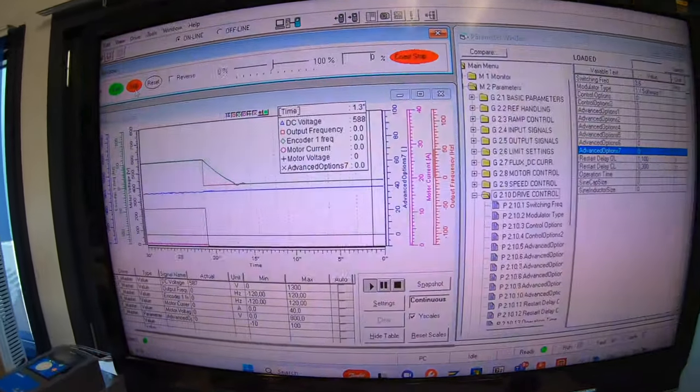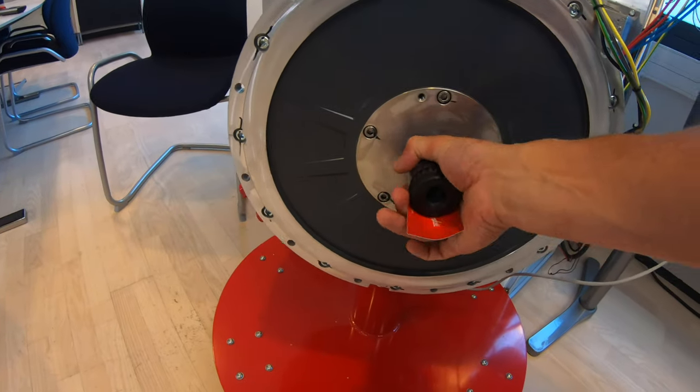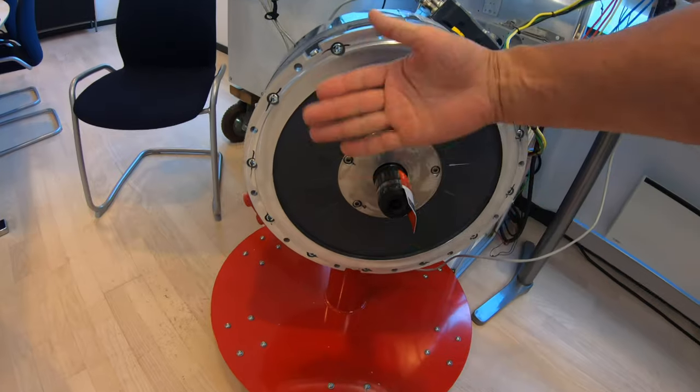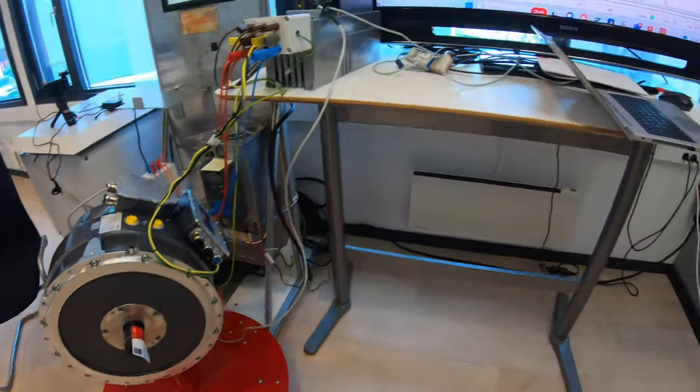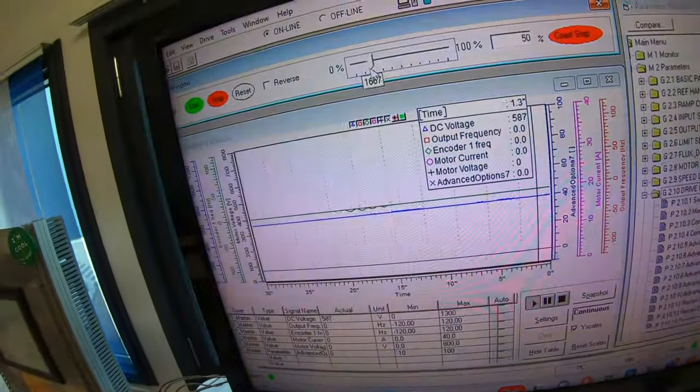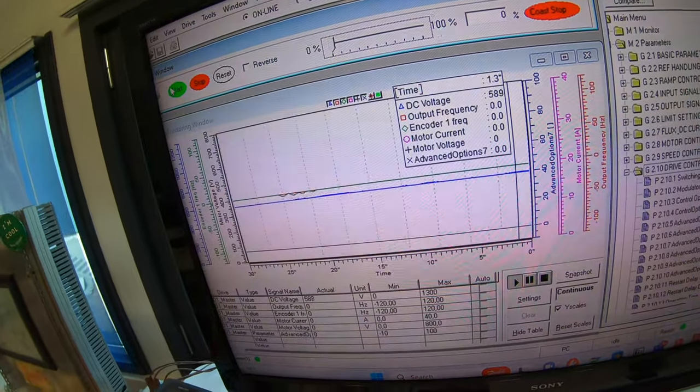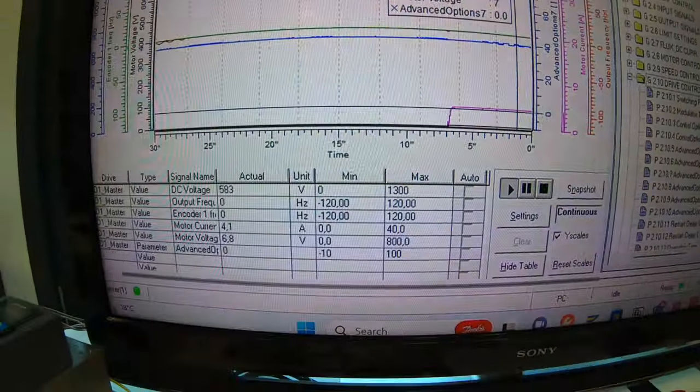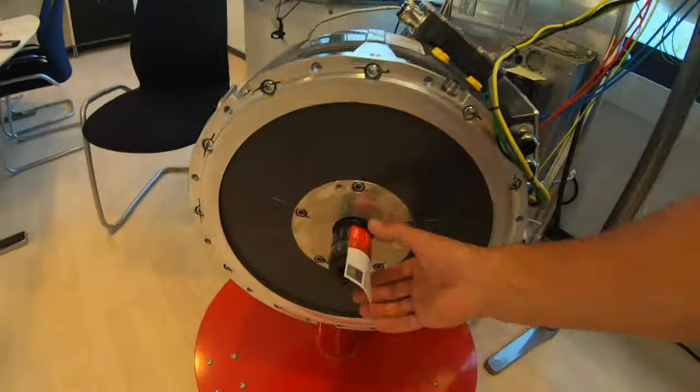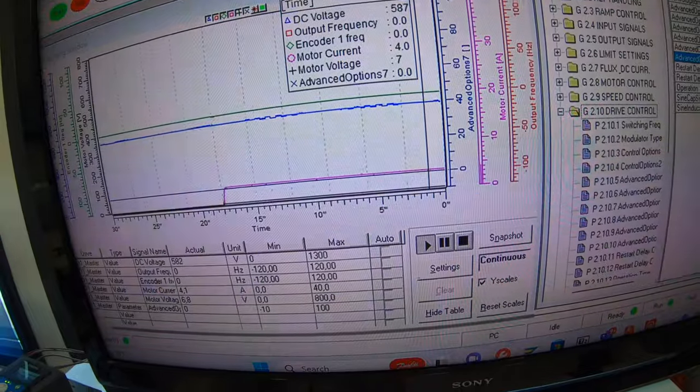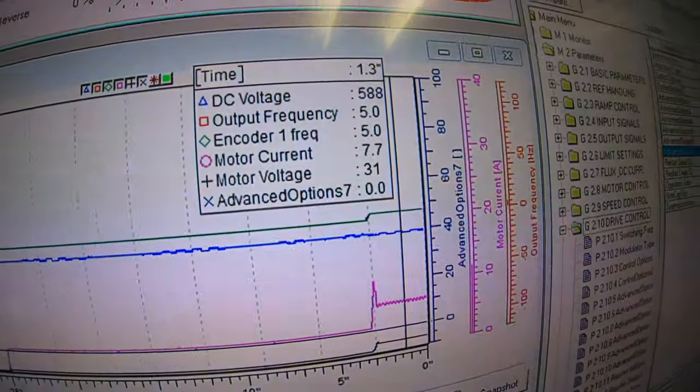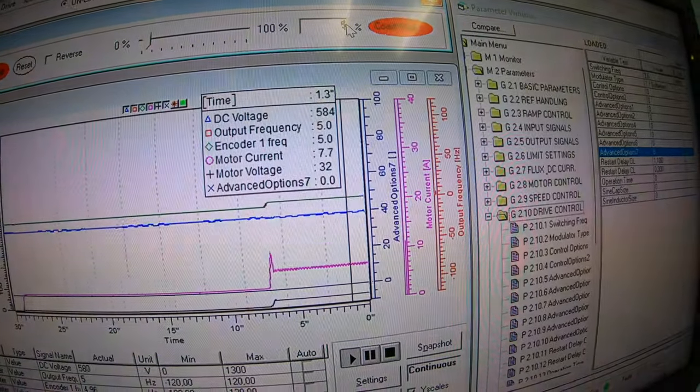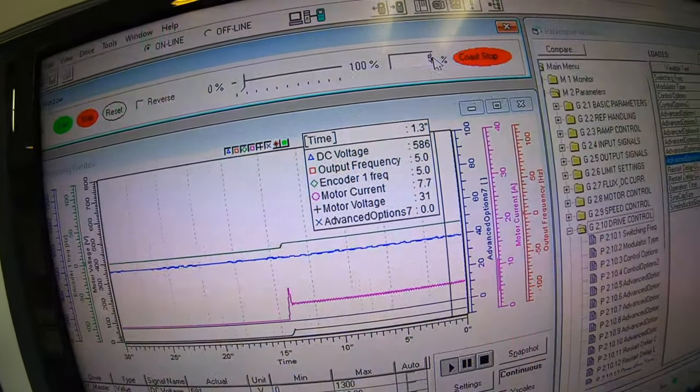Here we are ready for the first start up. Typically we start up at zero speed, and that is after we have made sure that the shaft is free rotating. If there is a gearbox or propeller here, if it is possible to disconnect, we do that. If the propeller is not possible to disconnect, zero pitch is a good thing. We start it at zero speed. Here we see a current of 4.1 ampere and a voltage of 7 voltage. If we want to run it at a very slow speed, 5% or something, here we can see that the output frequency is the same as the encoder frequency, so these ones actually run in the same direction. This is good.